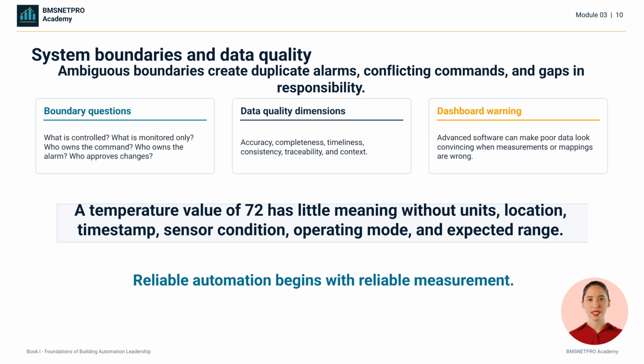Every BAS program needs explicit boundaries. Which systems are directly controlled? Which are monitored only? Which interface is read only? Which system owns the authoritative command? Which system owns the alarm? Which system stores the official history? When boundaries are unclear, you get duplicate alarms, conflicting commands, and gaps in responsibility. Data quality is also an engineering property. Accuracy, completeness, timeliness, consistency, traceability, and context all matter. A value of 72 is not enough information.